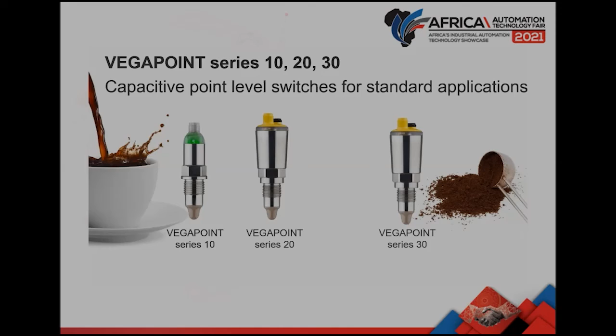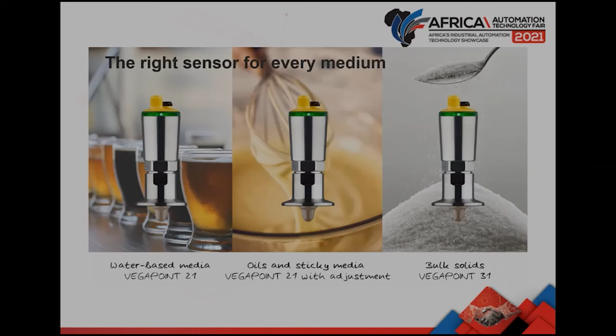The VEGAPOINT 20 and 30 are equipped with Bluetooth as well, in case of adjustment requirements. So you might want to use the VEGAPOINT 21, for example, on interface measurement between oil and water. The VEGATools app can be utilized, and simple adjustments can be made to make these devices suitable for applications besides low-level and high-level switches. So here again, we have the adaptable feature on the VEGAPOINT. With the threaded version, we can take the hygienic adapters that are all FDA approved, and we can screw them onto the level switch. And we've converted this into a fully hygienic level switch suitable for the food and bev and the pharmaceutical industry.